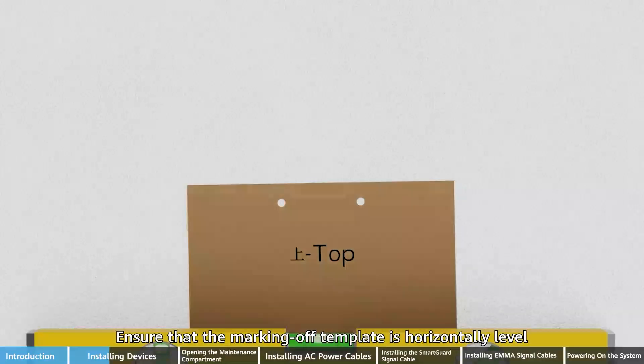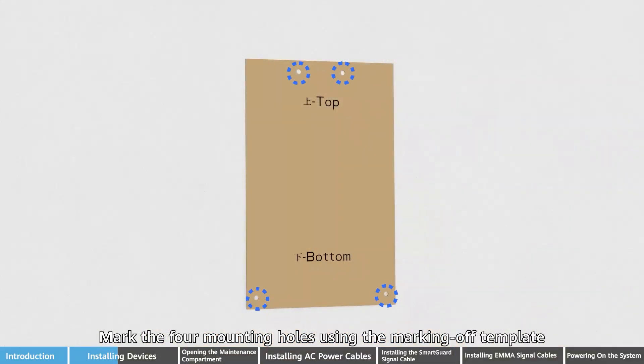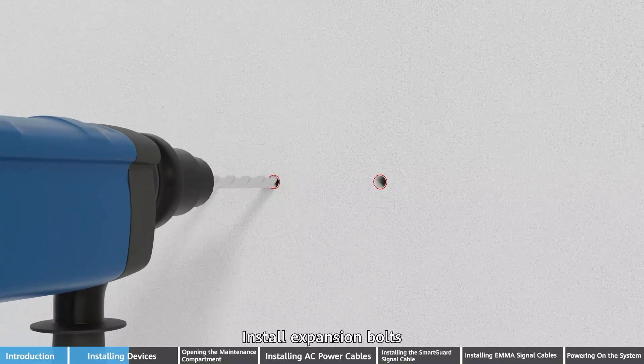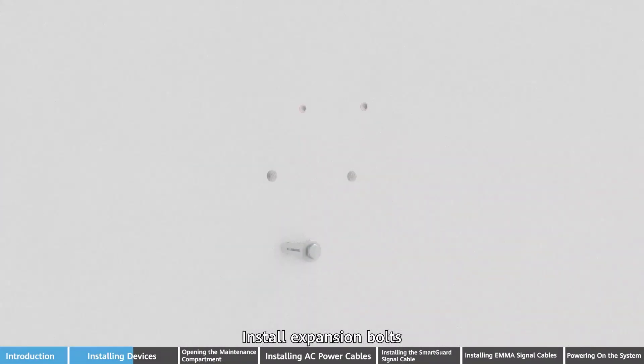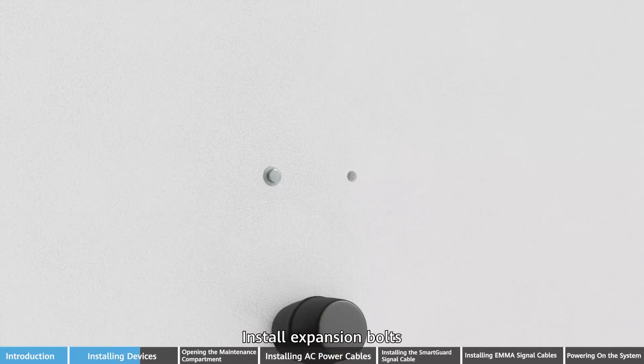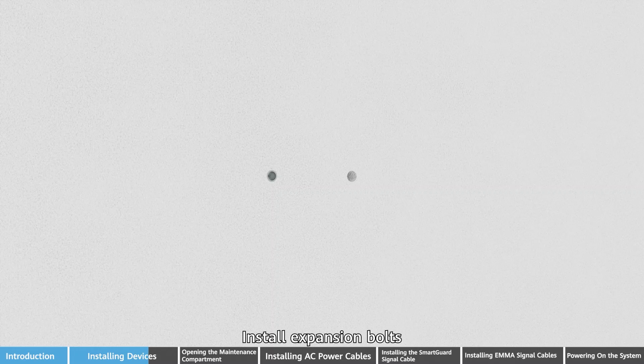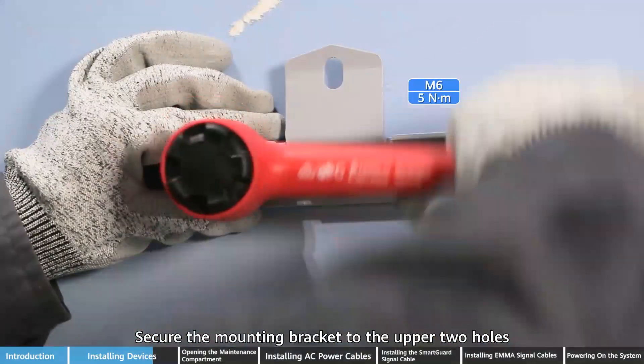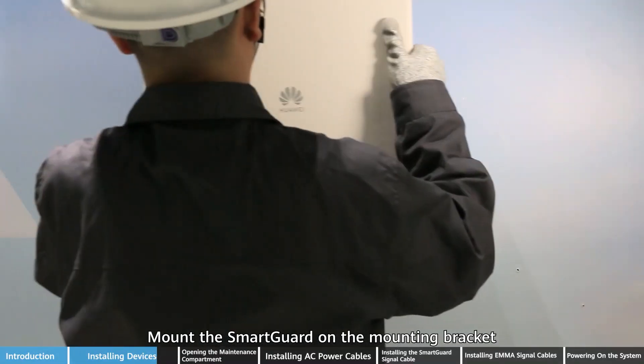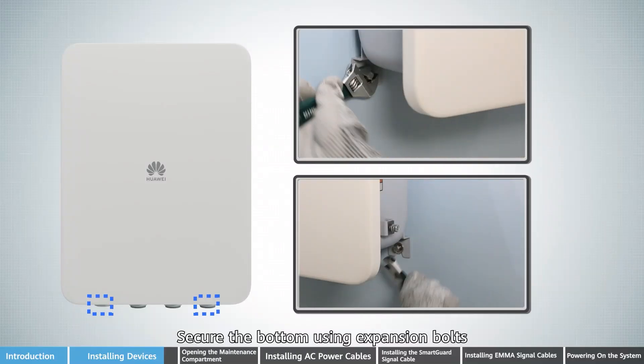Ensure that the marking off template is horizontally level. Mark the four mounting holes using the marking off template. Install expansion bolts. Secure the mounting bracket to the upper two holes. Mount the SmartGuard on the mounting bracket. Secure the bottom using expansion bolts.